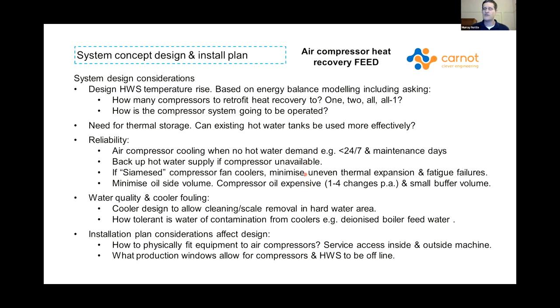And when you get into the insides of the compressors, you need to be aware that you're not creating extra stresses inside the machine, which can cause them to physically fail. So in some cases, the coolers, which are the air aftercooler and the oil cooler, are physically joined together as one solid block of aluminium. If you were to take heat out of the oil cooler and not out of the aftercooler, you could cause temperature differences in your cooler, cause them to stress and crack and fatigue. So you need to be very careful about those sort of scenarios.